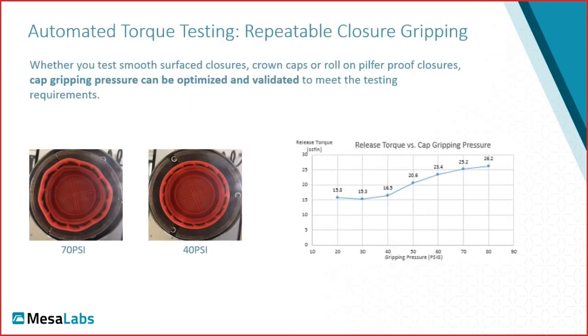With automated torque testing, we can ensure repeatable closure gripping. We either use a serrated chuck, but that's not in the picture below, or the pressure actuated chuck, which is demonstrated on this slide. As you can see, this is a pressure sensitive cap, and at 70 psi gripping pressure, you can see how the cross section is becoming oval and distorted. And at 40 psi, which was optimized for proper gripping, the cross section is not affected, so we would get accurate torque readings. That's just to point out that sometimes it's not enough to change to an automated tester, but it's important that you find the right settings for that automated tester.